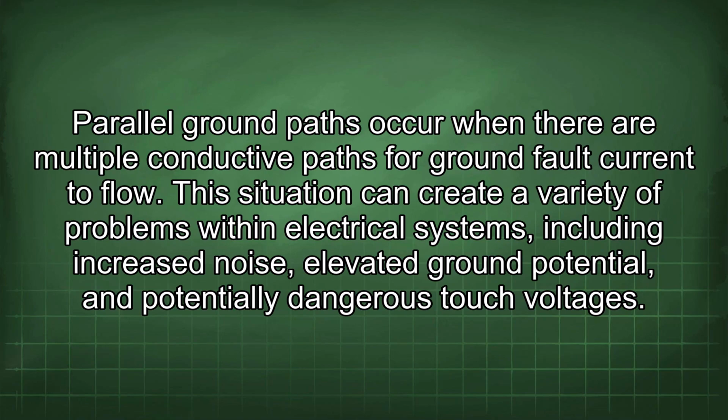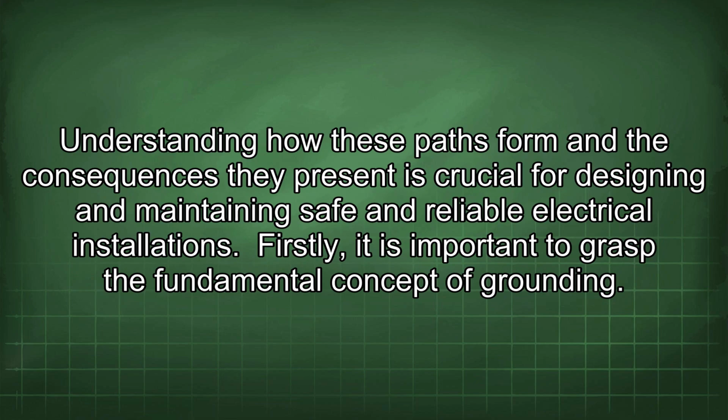Parallel ground paths occur when there are multiple conductive paths for ground fault current to flow. This situation can create a variety of problems within electrical systems, including increased noise, elevated ground potential, and potentially dangerous touch voltages.